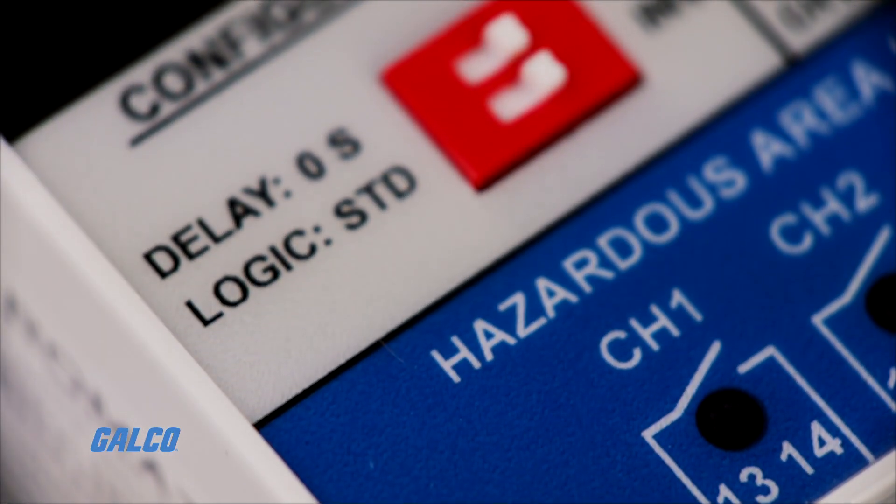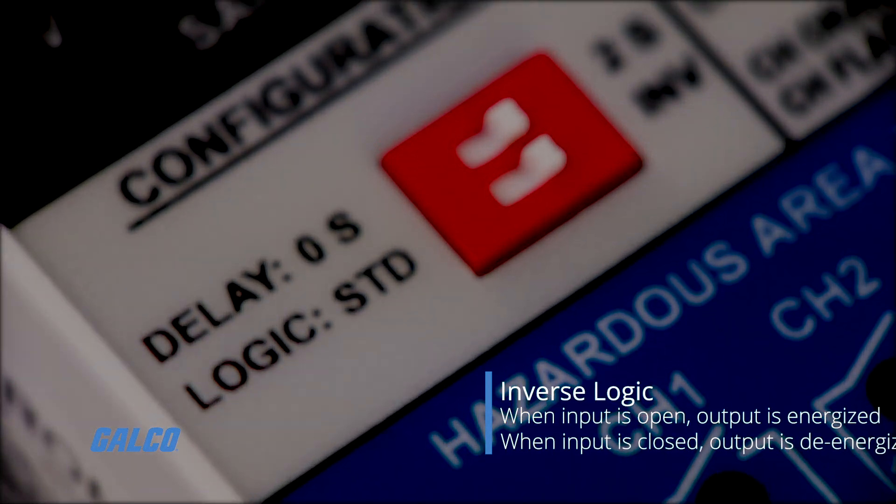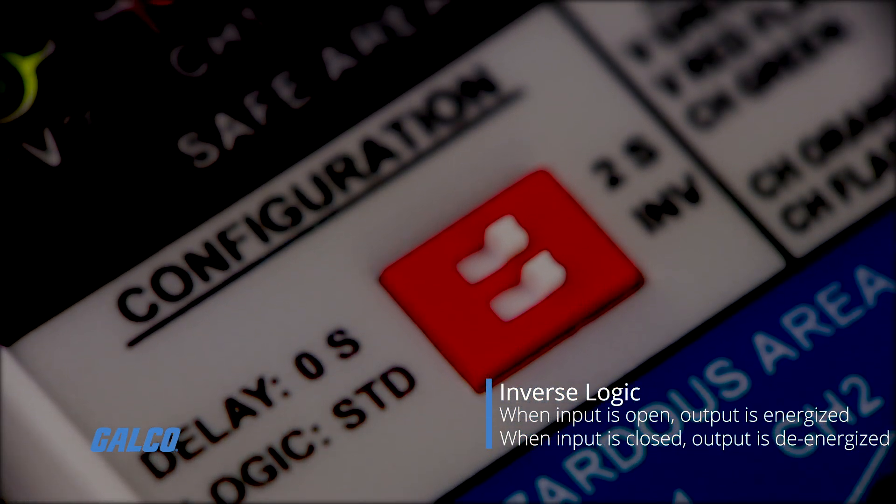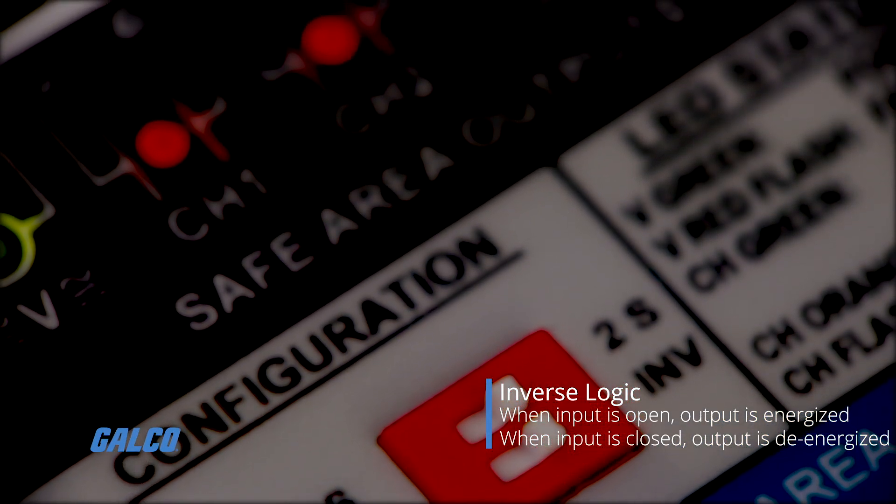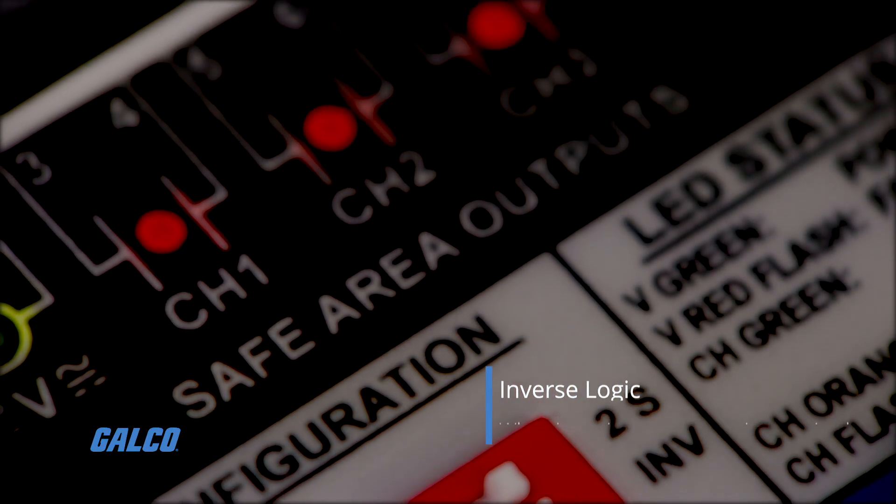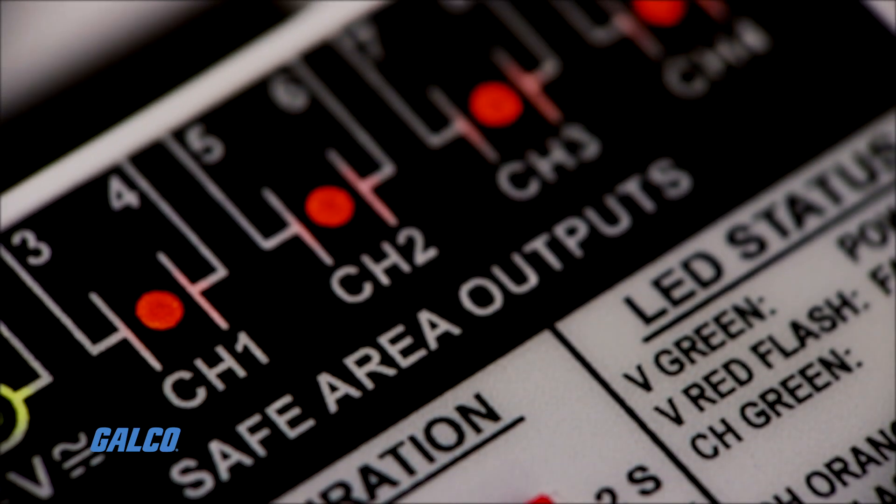Inverse Logic: When the input device in the hazardous area is open, the corresponding output relay is energized. When the input device closes, the corresponding output relay will de-energize.